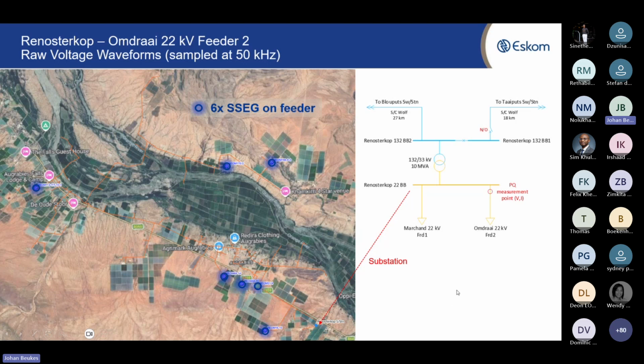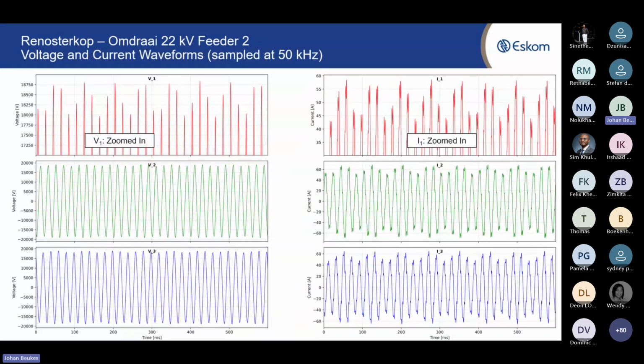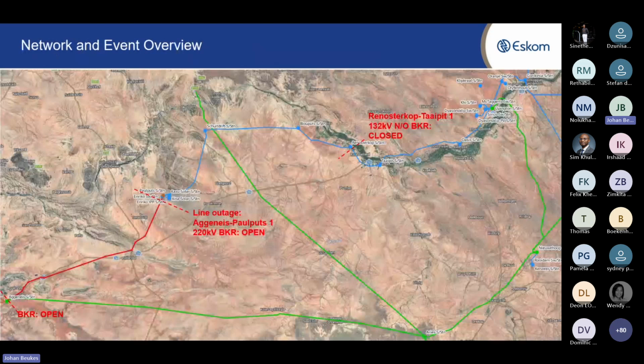So we were measuring harmonics, and then I realized that there was severe flicker on that particular feeder. We realized it by seeing the lights flicker in the lodge that we stayed in, and when we measured it, these are the oscillations that we saw in the current and voltage waveforms on that feeder. When we started investigating, we realized there was a line in the Northern Cape out. It was the Aggeneys-Paulputs line that was out for 1 or 2 days for maintenance.